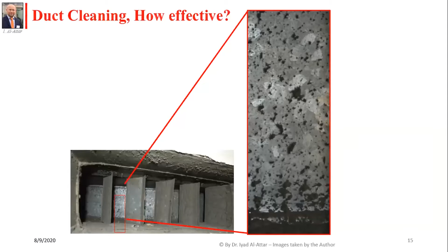The equation is simple, and this is something I've experienced myself. This is a fan coil unit that uses a metallic filter, and you can see how the coil looks and what the diffuser ends up looking like. What I did for this fan coil unit was make some replacements, increasing the efficiency as much as possible within the allowable pressure drop. With a 45% efficiency layer of filtration, we got the coil much cleaner and the diffuser definitely cleaner than what you see on top.